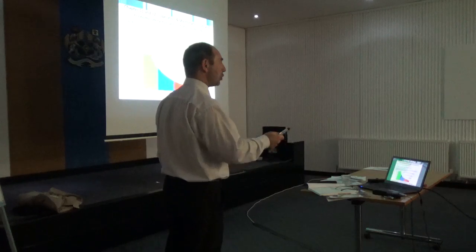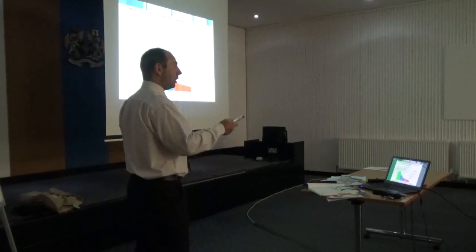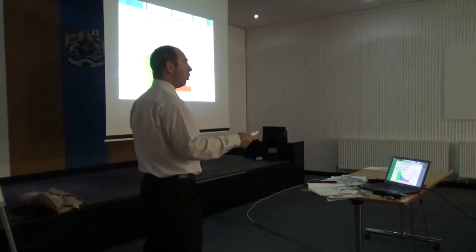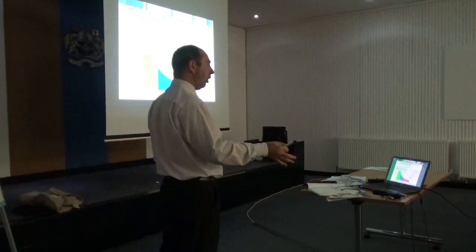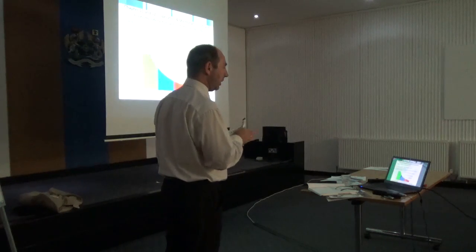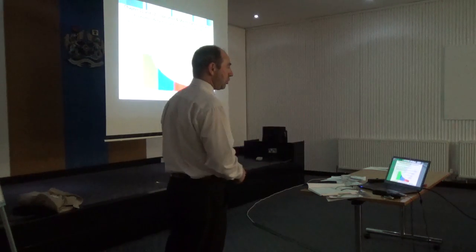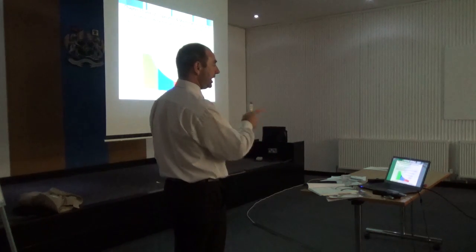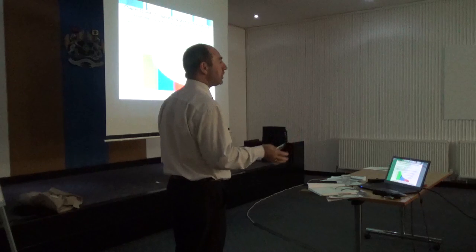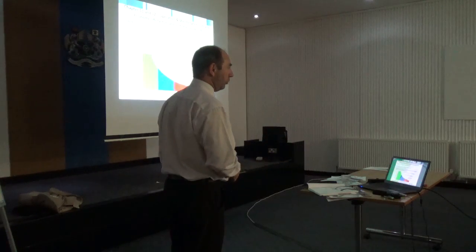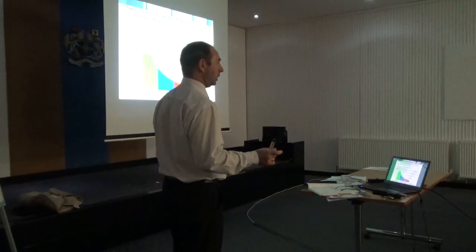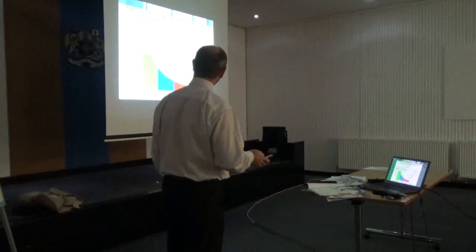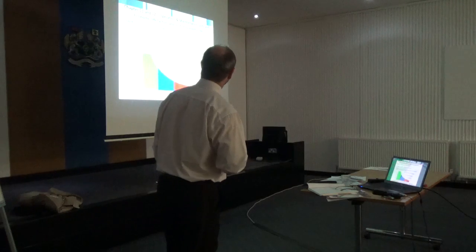Is the cost that I've saved likely to be fully recovered, or is it now going to cost me more to deal with the backlog? Probably not, but I would suggest that if you saved £100,000 by doing statutory only, in dealing with the backlog, you might still have to spend £80,000. It's not what you think. The return and the saving is not demonstrable.